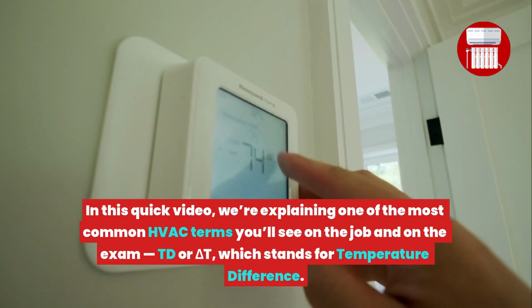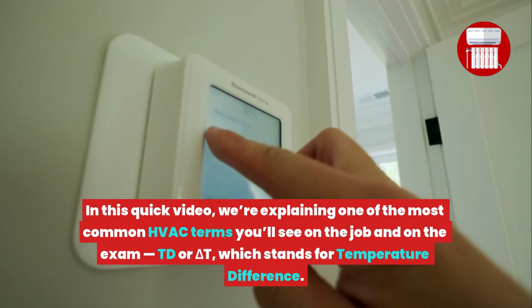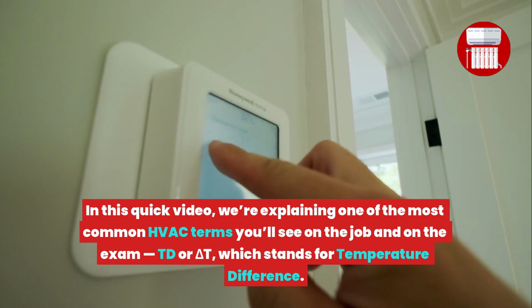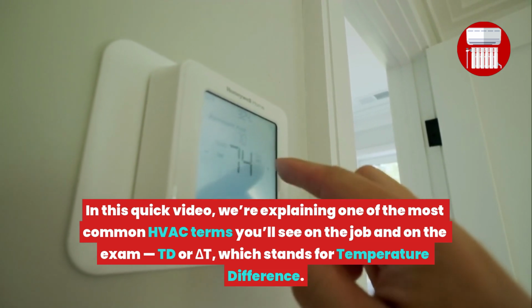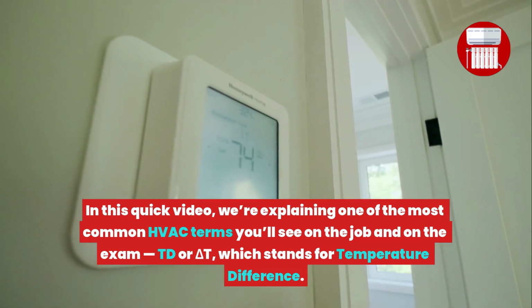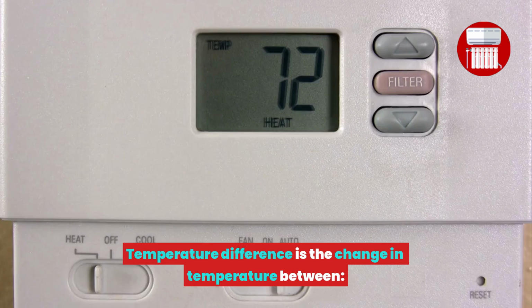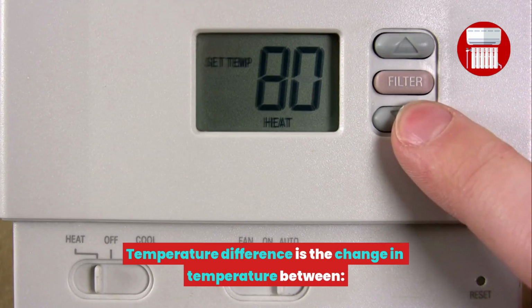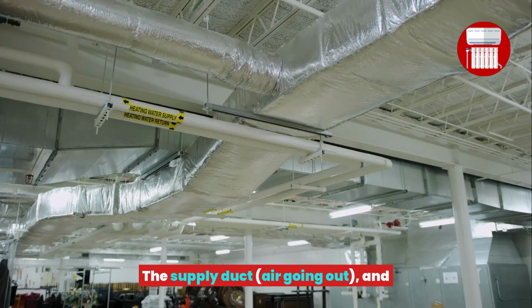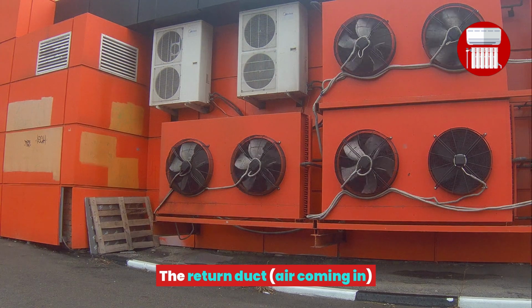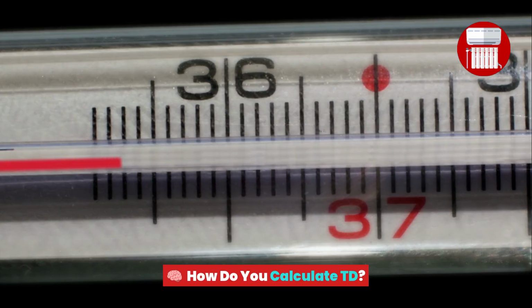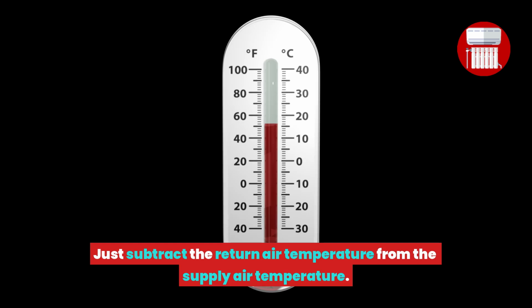In this quick video, we're explaining one of the most common HVAC terms you'll see on the job and on the exam, TD or ΔT, which stands for temperature difference. What is TD? Temperature difference is the change in temperature between the supply duct, air going out, and the return duct, air coming in. How do you calculate TD? Just subtract the return air temperature from the supply air temperature.